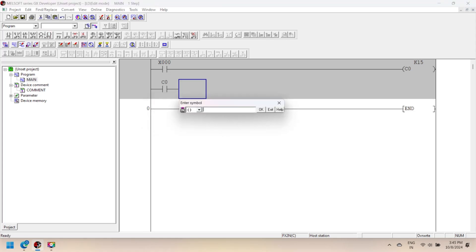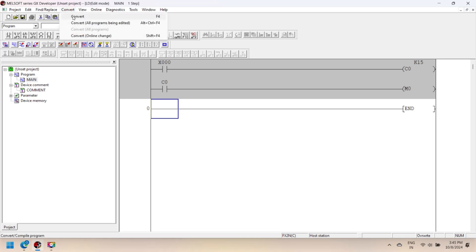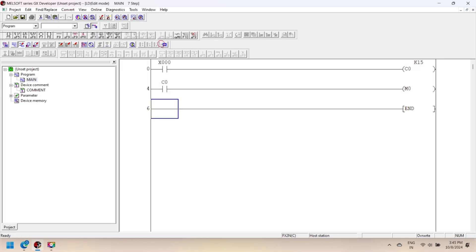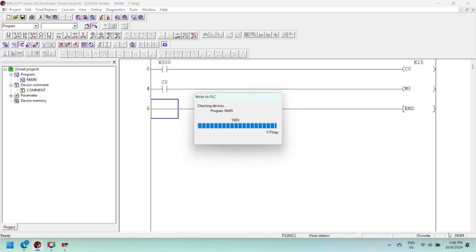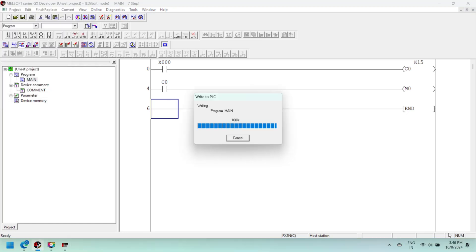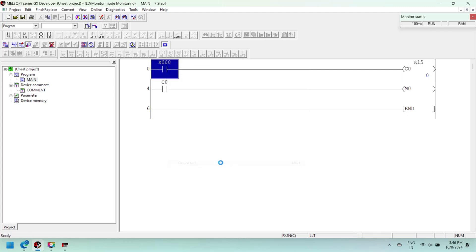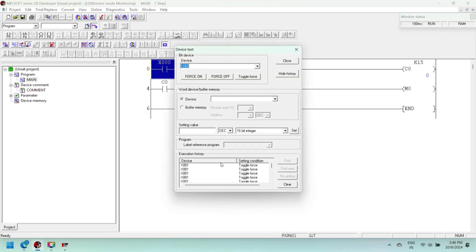A counter is used as an output instruction with some preset value. The range of the preset value depends on which type of counter device is used. Now download your program to the controller — I am using a PLC simulator. In this program, X000 is the input of the counter, C0 is the counter device, 0 is the counter number, and the counter preset value is defined as K15, so the counter increments its current value to reach the counter preset value.